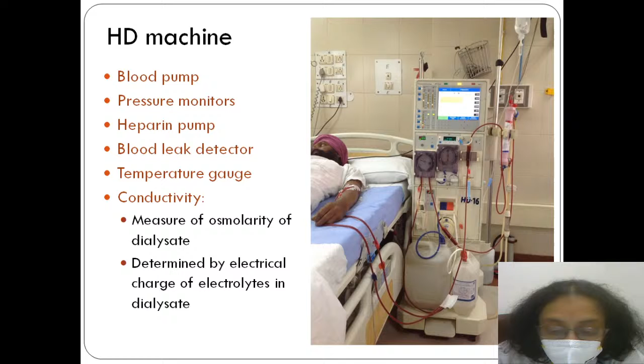to give. So suppose you want to give a 4-hour dialysis session and you want to ultrafilter 2 liters of fluid during that. So you put in 4 hours and you put in 2 liters. So the machine will remove 500 ml per hour of fluid. And you can also see the osmolarity of the dialysate, which is an indirect estimate of the electrolyte and the electrical charge, which determines the sodium content. You can vary the sodium content of the dialysate fluid, and you can also add potassium into the dialysate fluid if a patient has hypokalemia.